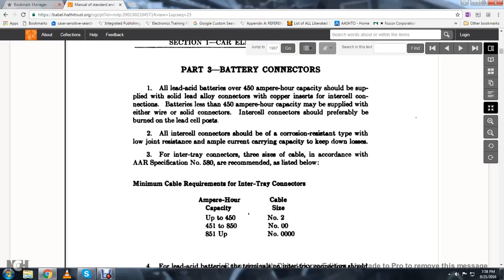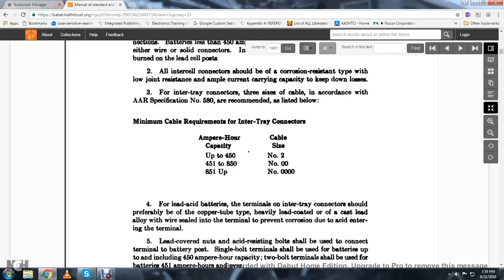For inter-tray connectors, three sizes of cables in accordance with American Railroad Specification No. 580 are recommended. Minimum cable requirements for inter-tray connectors by ampere capacity: up to 450 ampere hours, cable size number two; 451 to 850 ampere hours, double-zero gauge; 851 and up, four-zero gauge.